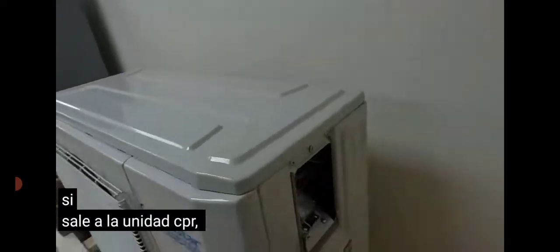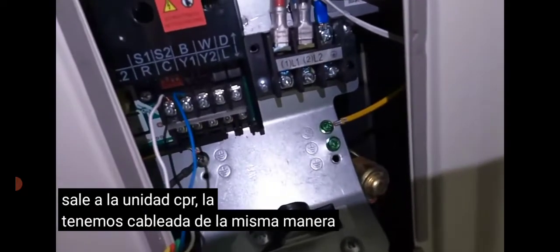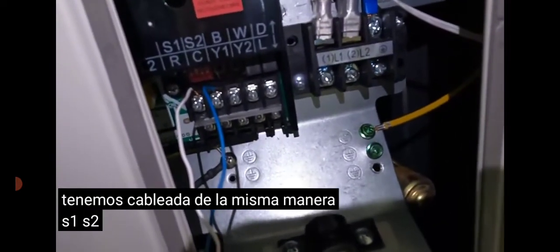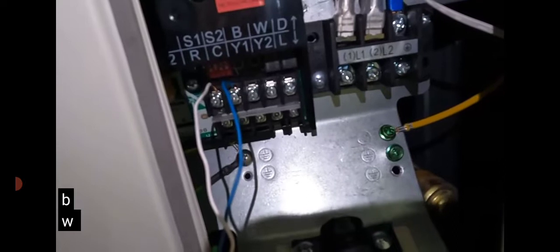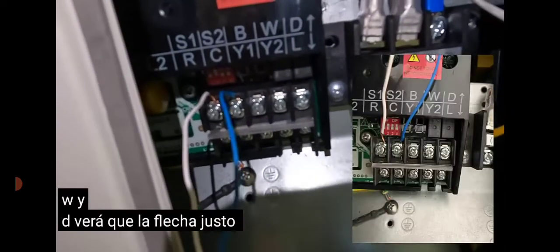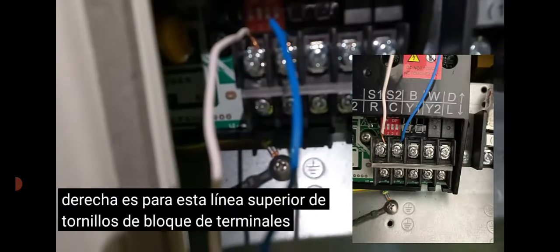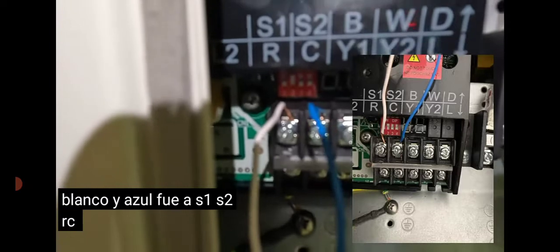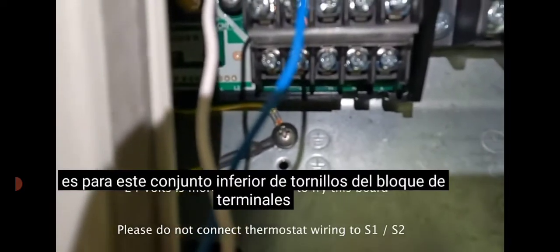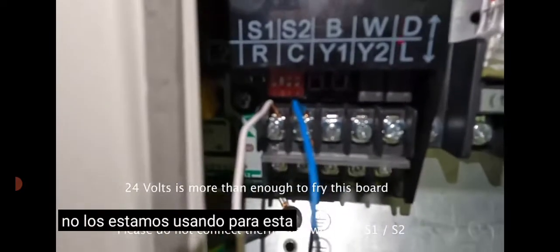If you come out to the CPR unit, we have it wired just the same: S1, S2, B, W, and D. The arrow just to the right is for this top line of terminal block screws. White and blue went to S1, S2. R, C, Y1, Y2 is for the bottom set of terminal block screws. We're not using those for this wiring setup.